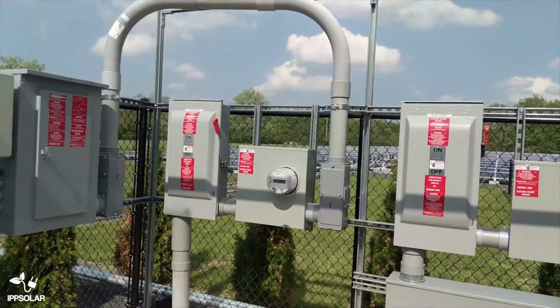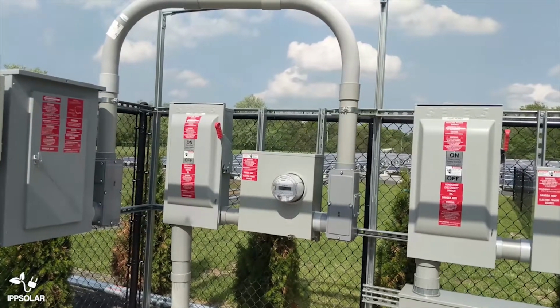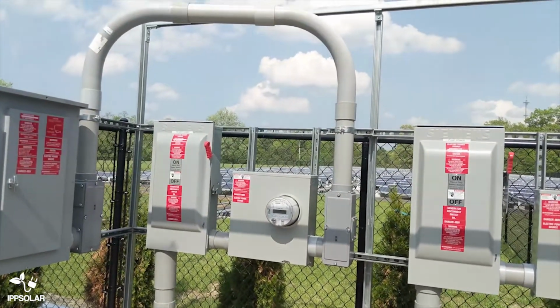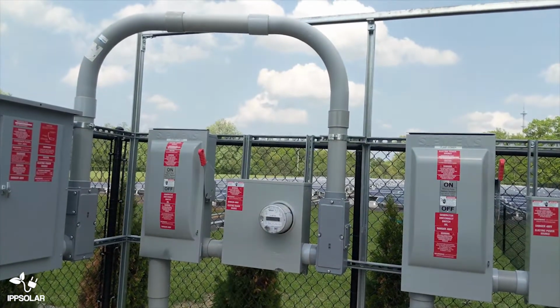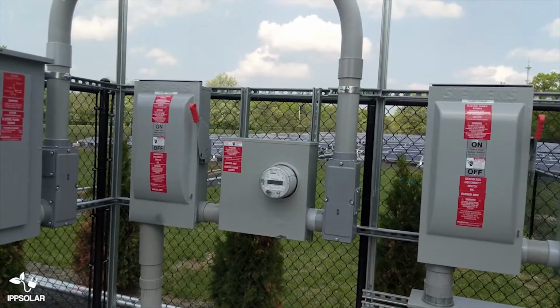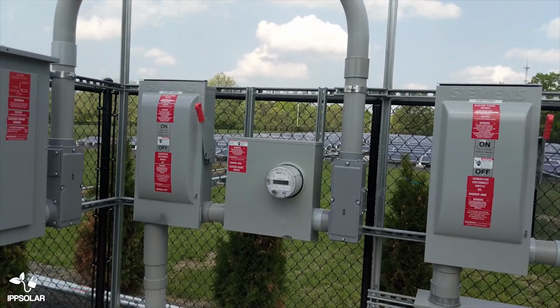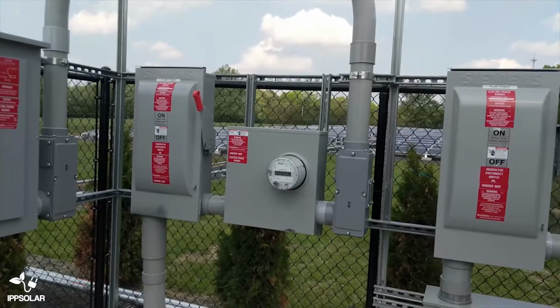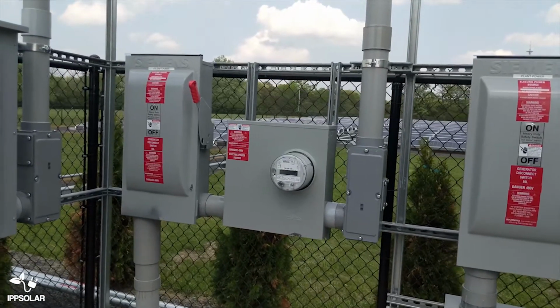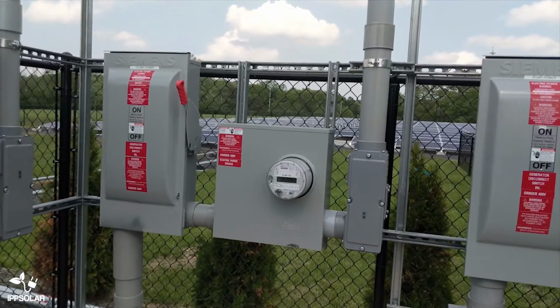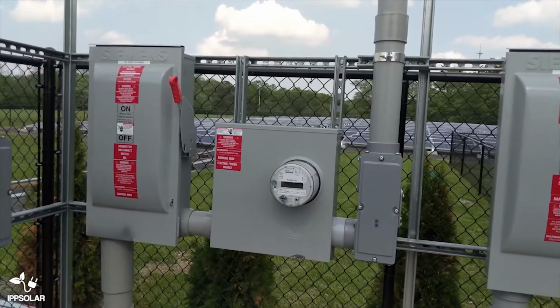The second way to measure the performance is by looking at the REC meter. Some states require a REC meter, like New Jersey or Connecticut, because the incentives are performance-based. In New Jersey, you have SRECs. In Connecticut, you have ZRECs. So that's another way to measure performance, and the numbers can be compared with what was provided by the inverters.